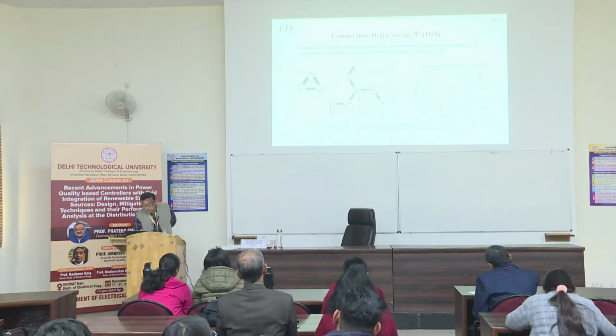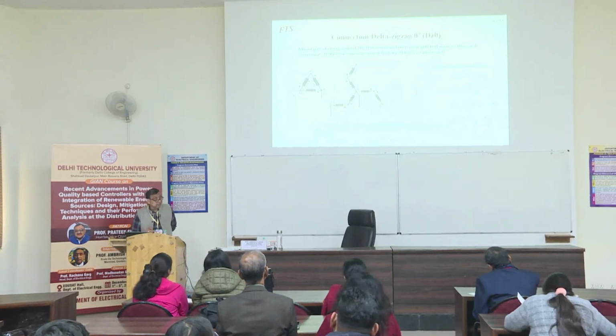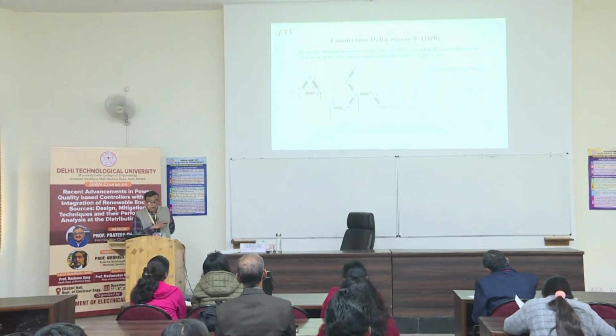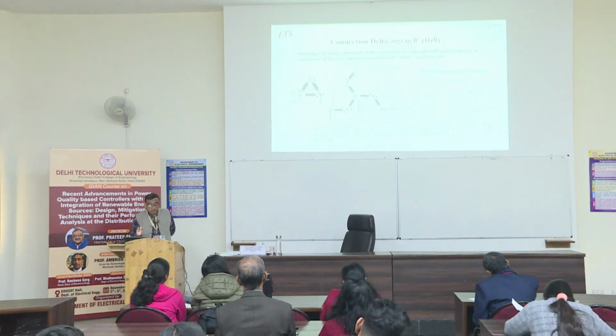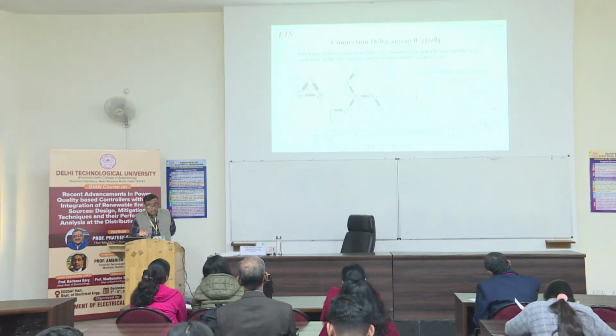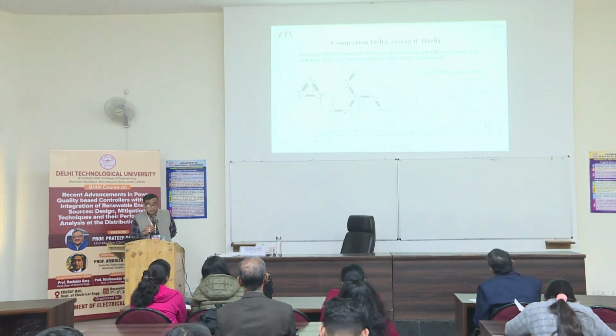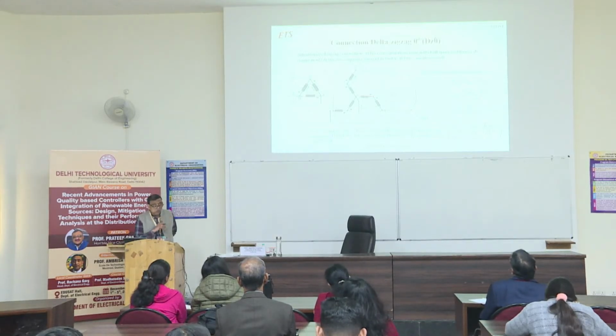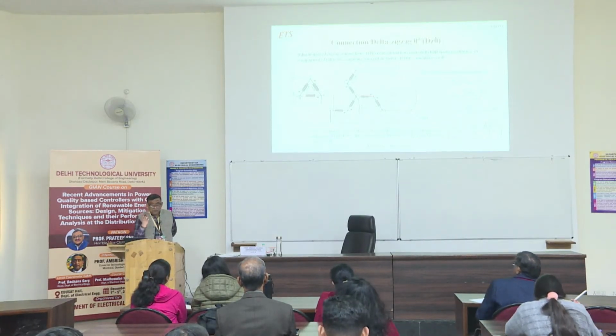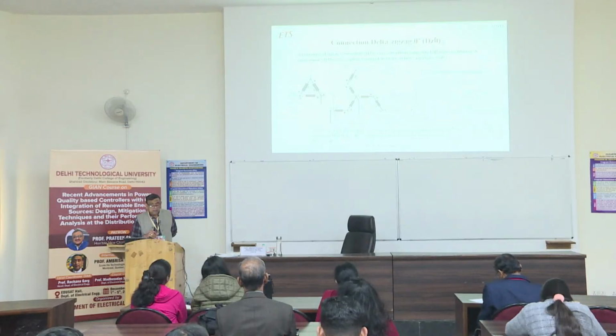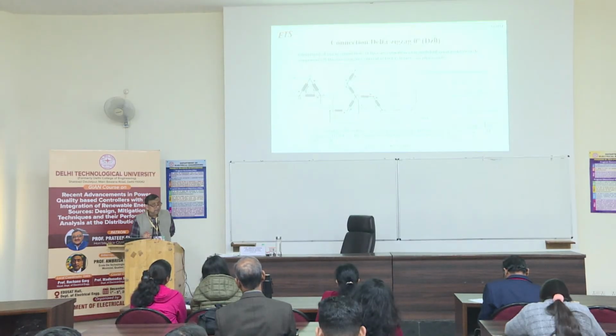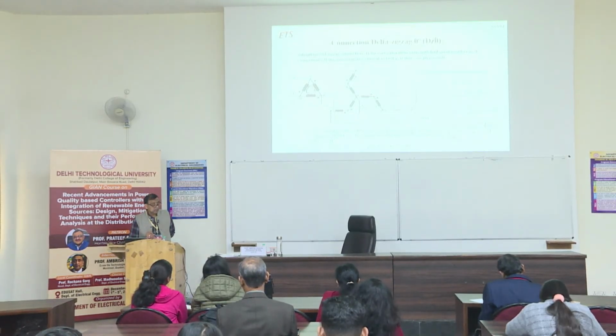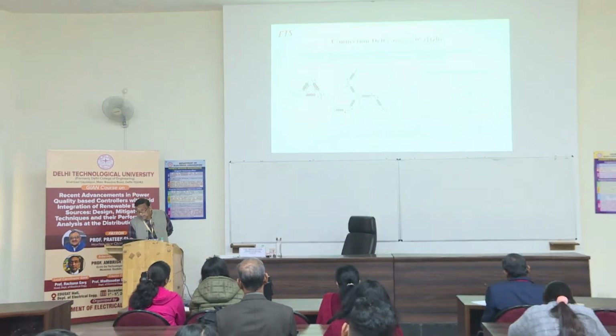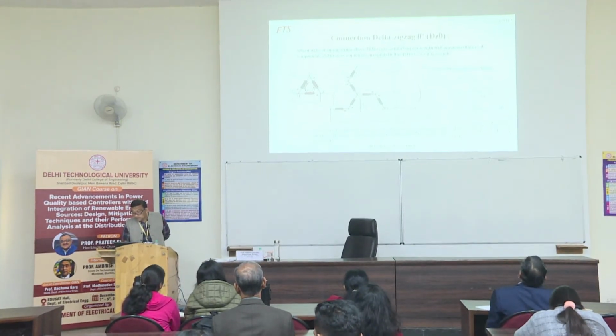No zero sequence current in delta. This is the way. But if you have YD11 or YD1, zero sequence currents are trapped in the delta. So although they are not going out, they are heating up the transformer. Right? So this is the disadvantage. But if you are using zigzag connection, even here you don't have the zero sequence current. And there is no phase shift if you have DZ0.